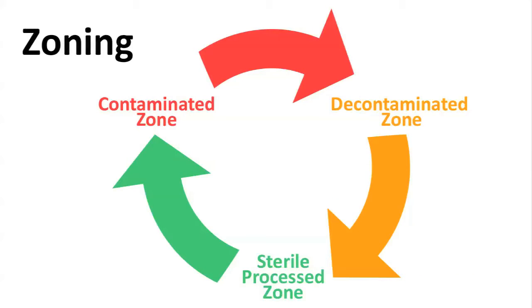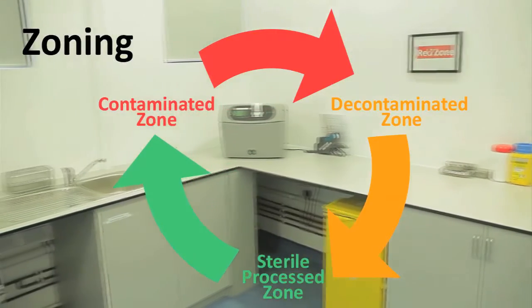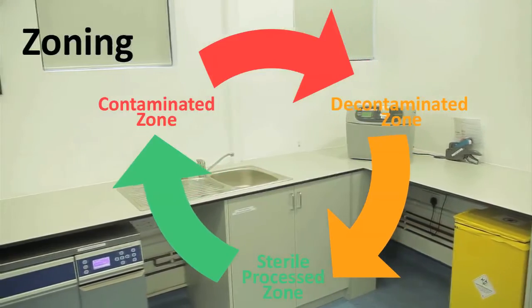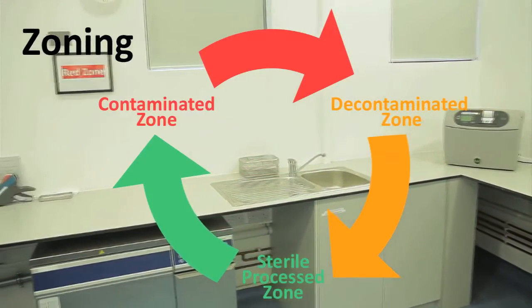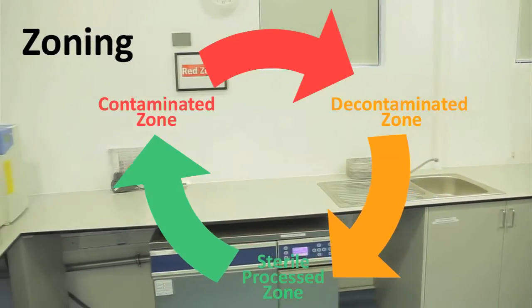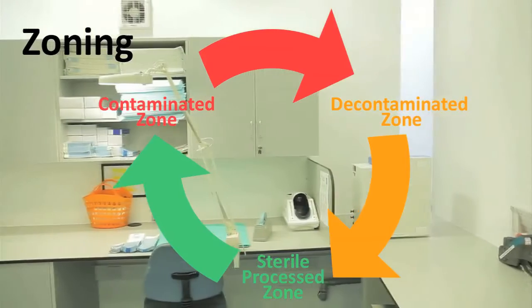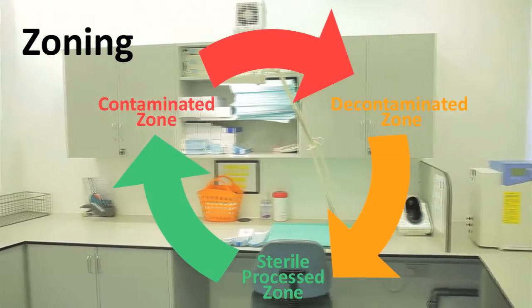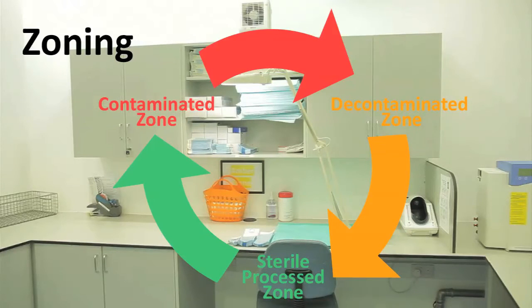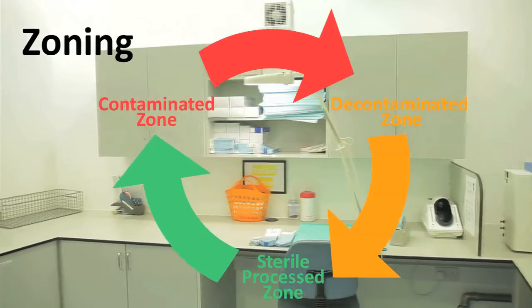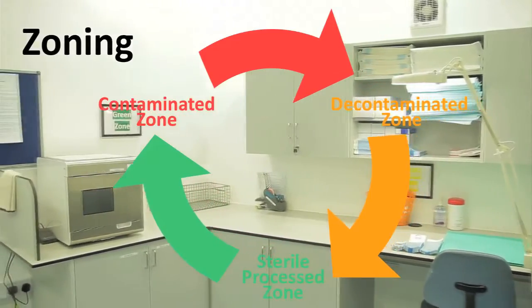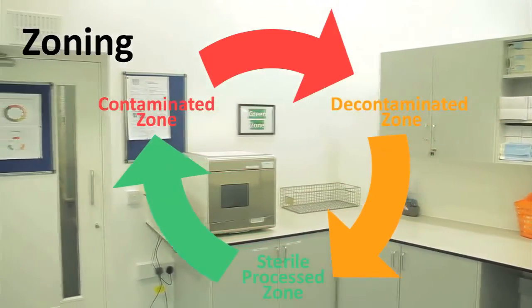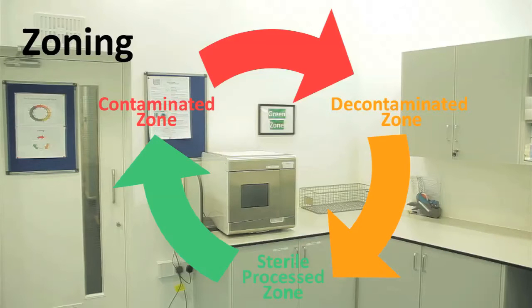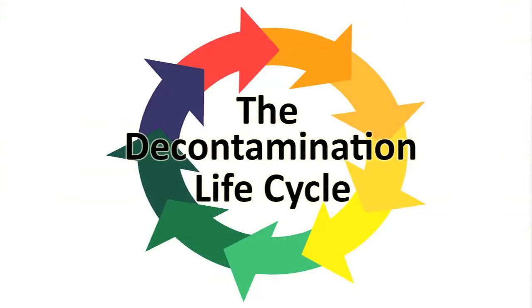The first zone is the red zone. This zone is the first point of contact in the LDU for reusable invasive medical devices, i.e. dental instruments, after they've been used on the patient. This is the most contaminated zone of all 3 zones. The next zone is the amber zone. Here instruments have been thermally disinfected but are not sterile. This zone should only be used to inspect, pack and prepare instruments for sterilisation. The last zone is the green zone. This is the zone from where instruments are released following steam sterilisation in an autoclave to the storage area before being used on a patient. In this video, we will accompany an appropriately trained dental healthcare worker through the steps of the decontamination life cycle.